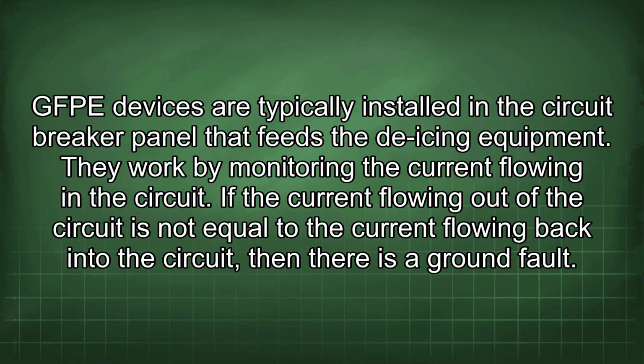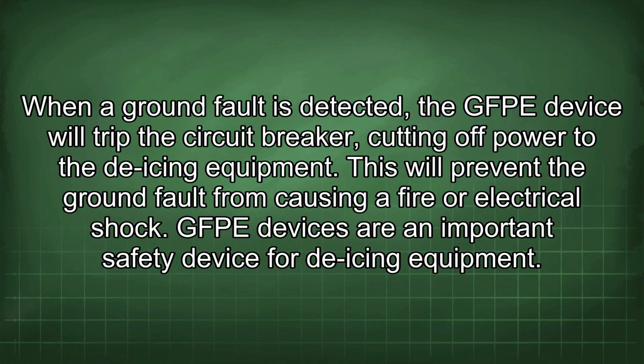GFPE devices are typically installed in the circuit breaker panel that feeds the de-icing equipment. They work by monitoring the current flowing in the circuit. If the current flowing out of the circuit is not equal to the current flowing back into the circuit, then there is a ground fault. When a ground fault is detected, the GFPE device will trip the circuit breaker, cutting off power to the de-icing equipment. This will prevent the ground fault from causing a fire or electrical shock.